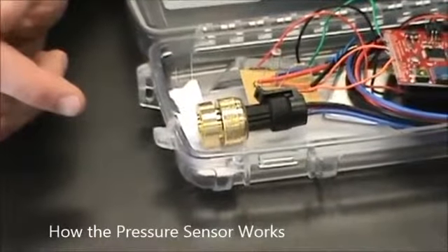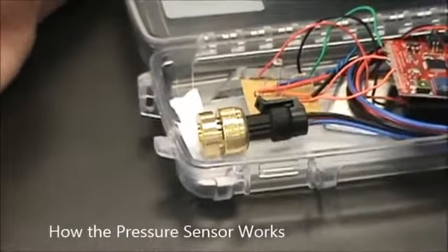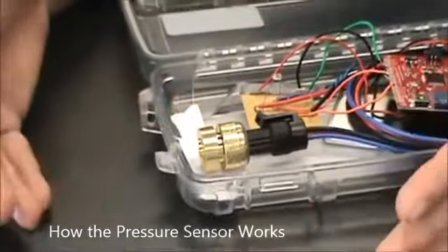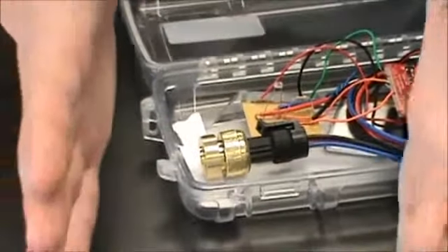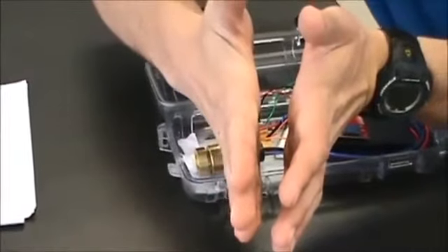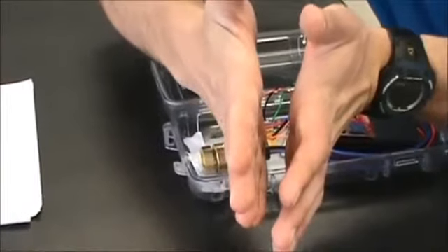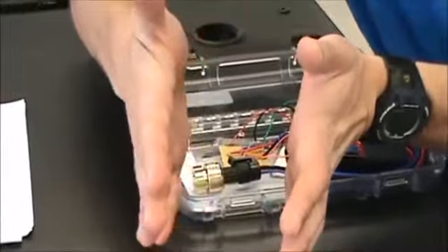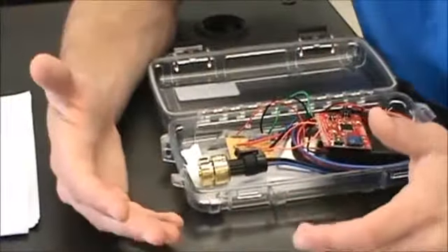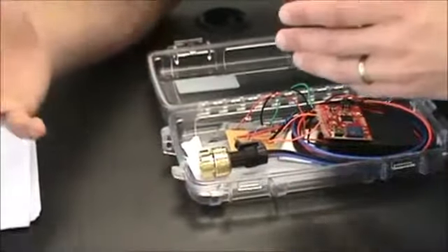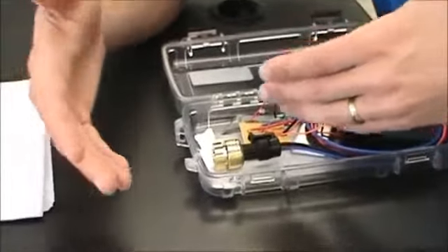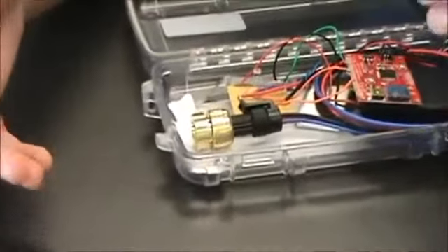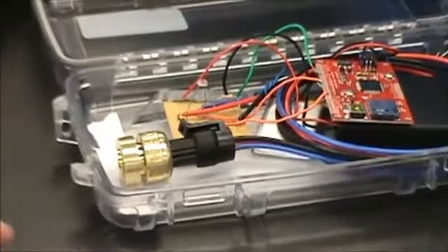The pressure transducer works using capacitance. So there's two plates inside it, and as water pressure comes in, you can imagine that the plates get pushed closer together. As they get closer together, the capacitance changes. So they're coming in, coming out. Capacitance will change, which leads to a voltage change, which is then output and measured. So that's how the pressure transducer works.